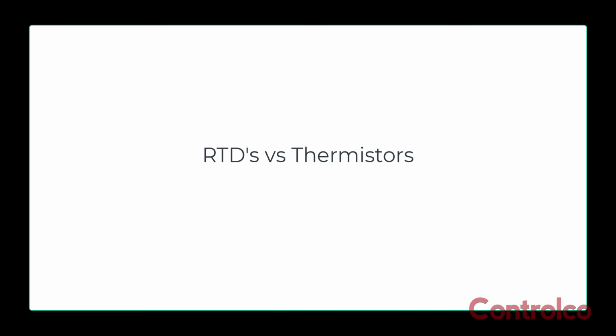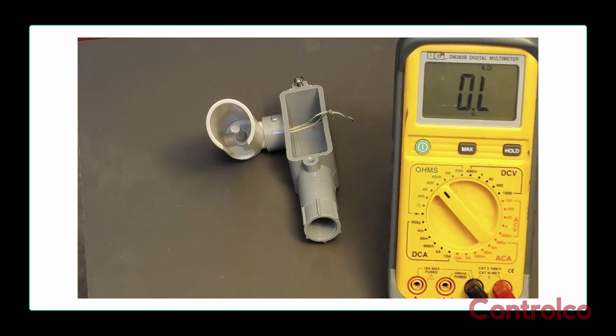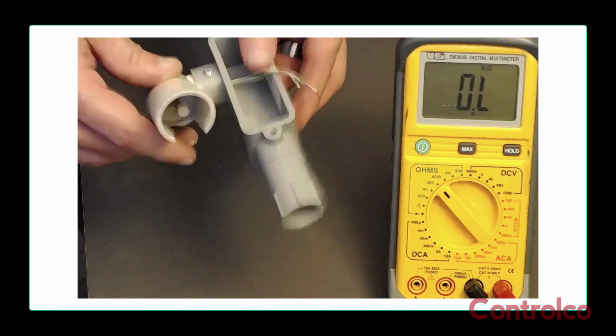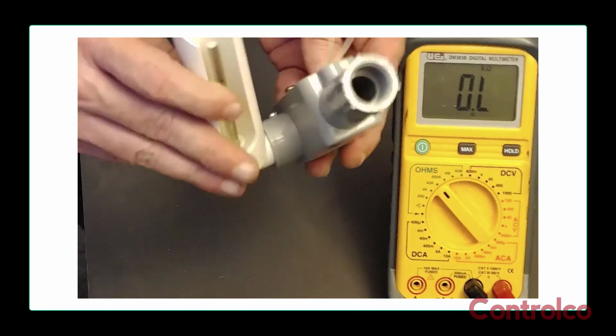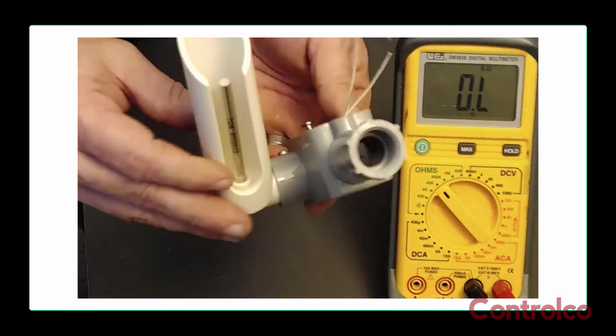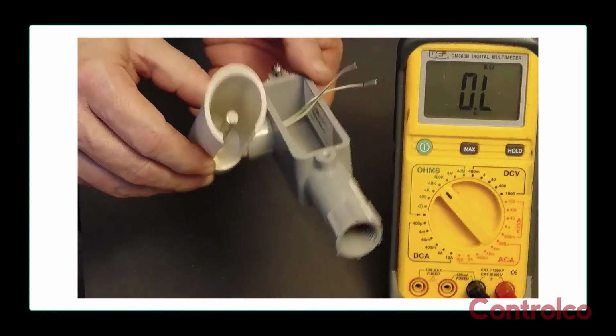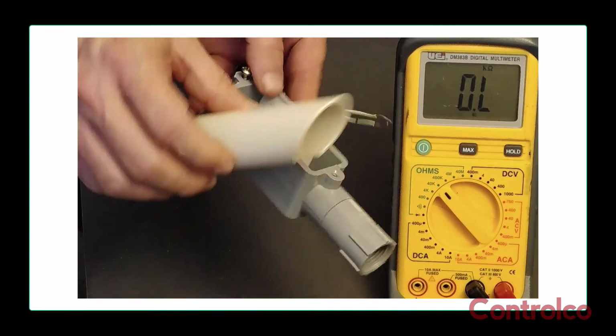I keep talking about being able to put a meter onto one of these sensors to test it out. So let me show you how you would go about doing that. So I happen to have this Johnson Controls outside air temperature sensor. It's 10,000 ohm. It's a thermistor. And you can see it's got a weatherproof housing on it and a sun shield, so it's designed for mounting on the outside of a building. So when you're picking out sensors, those are the things that you're going to keep in mind.